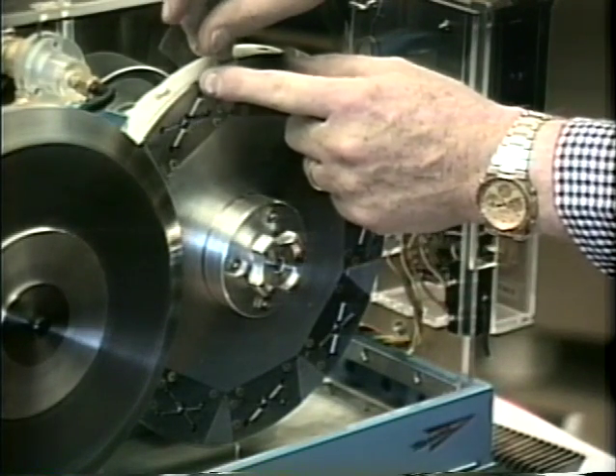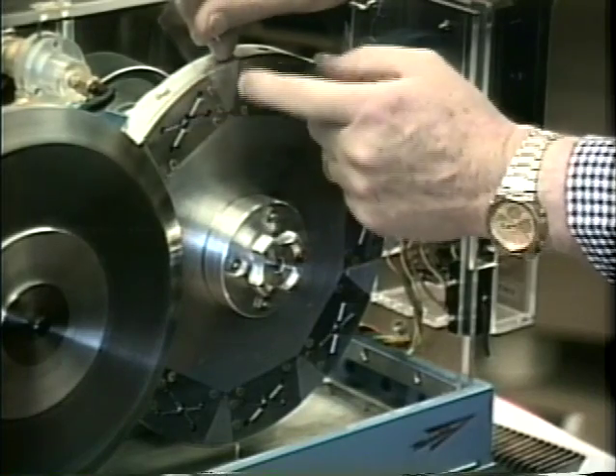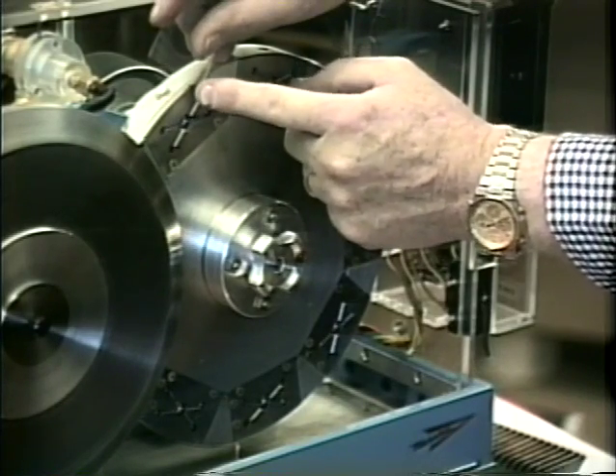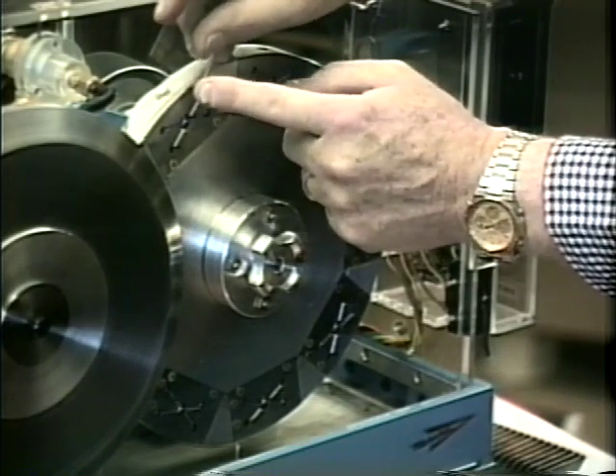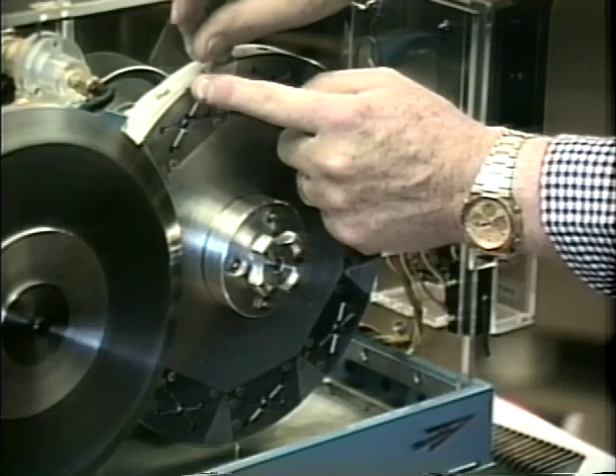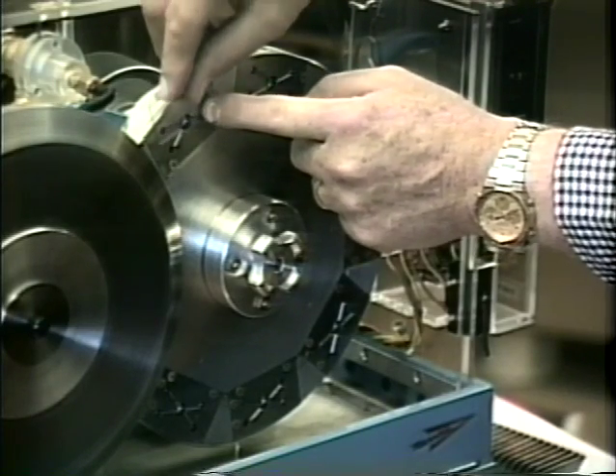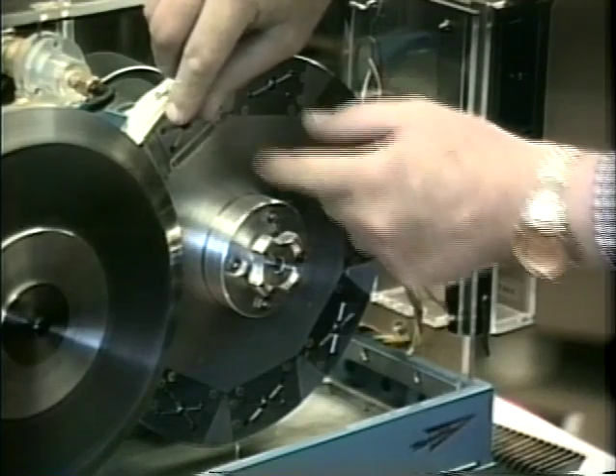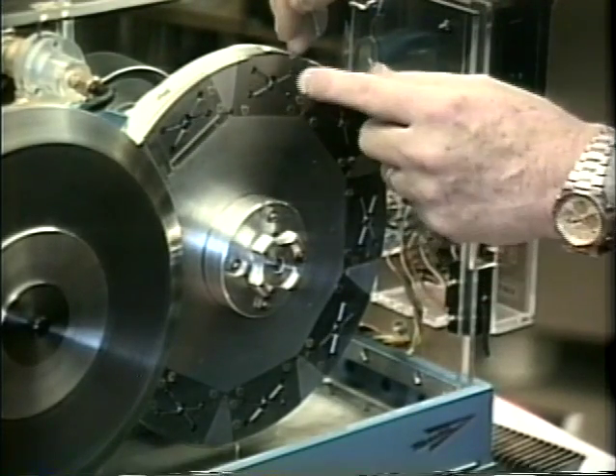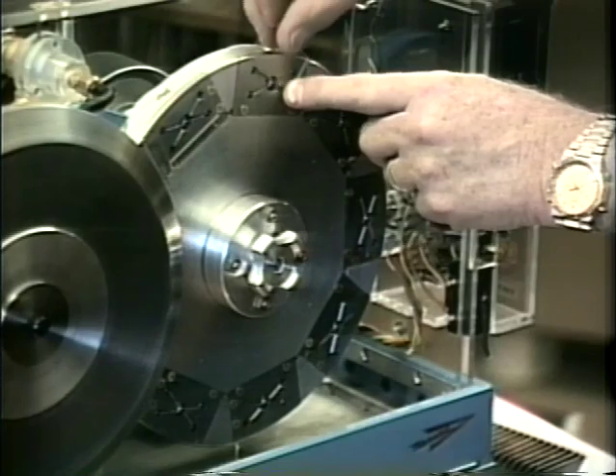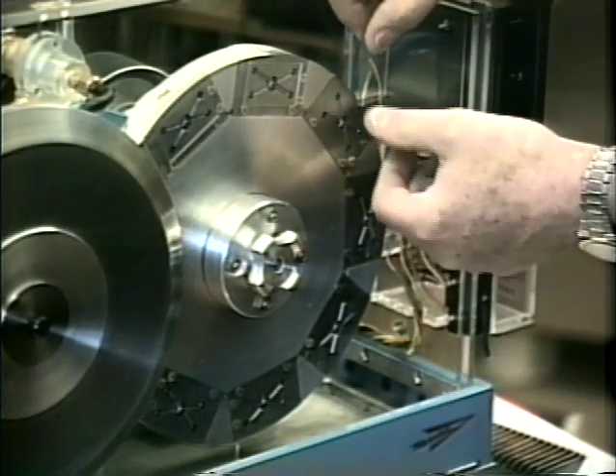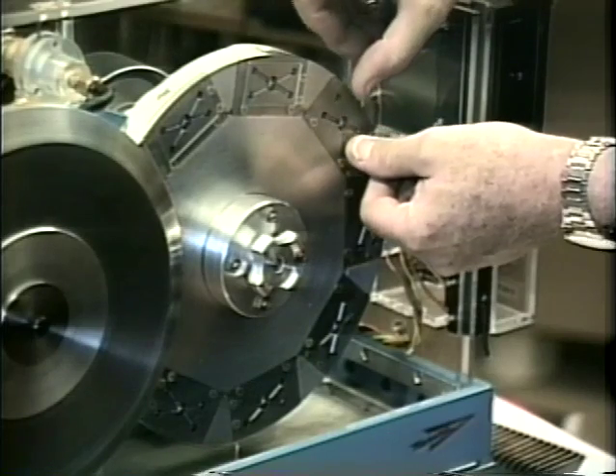Now to start the slides, you place a corner of the slide, triangular corner, into the station area and then slide the glass into position. So that's station number 1. There's number 2. And the vacuum is holding the glass on the chuck.